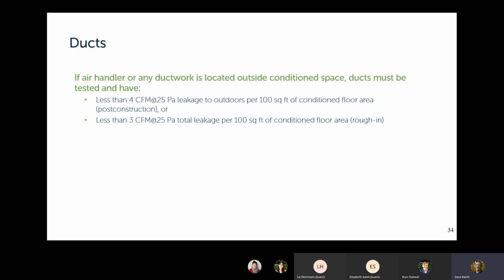And if the air handler, also known as the furnace, or any ductwork is located outside the conditioned space, ducts must be tested for air tightness. So this is a pretty vigorous requirement. Note that it only kicks in if you run your ducts outside the insulation layer. And the real intent here in the code, I believe, is not to punish people for running them outside as much as to discourage people from doing that in the first place. And this is entirely appropriate because running your heating and cooling ducts outside of the thermal envelope is just plain stupid, and comes with a fairly high performance penalty.